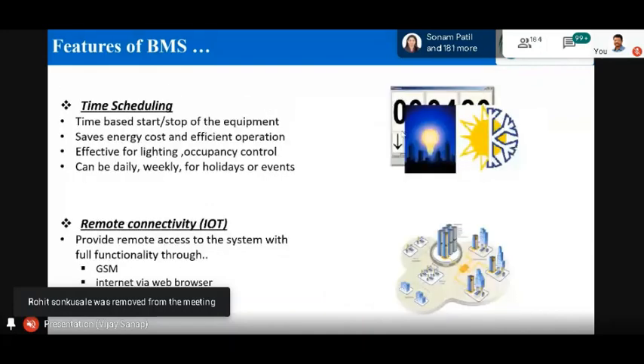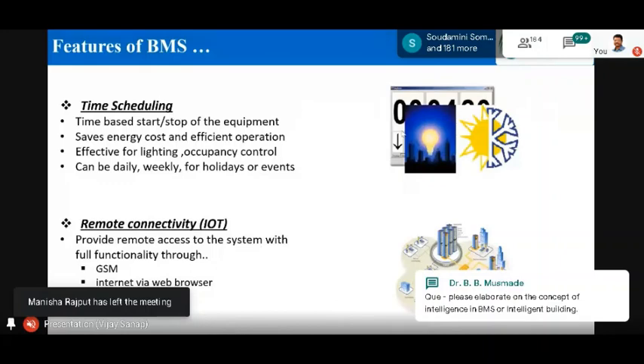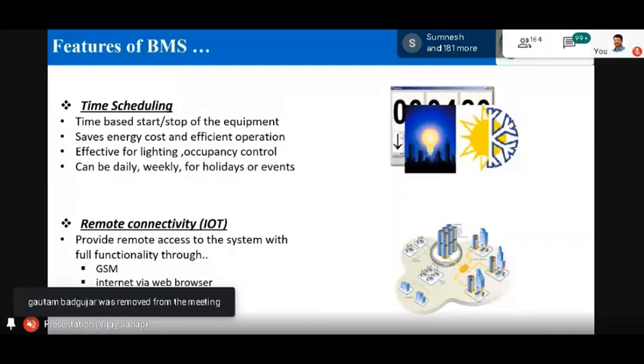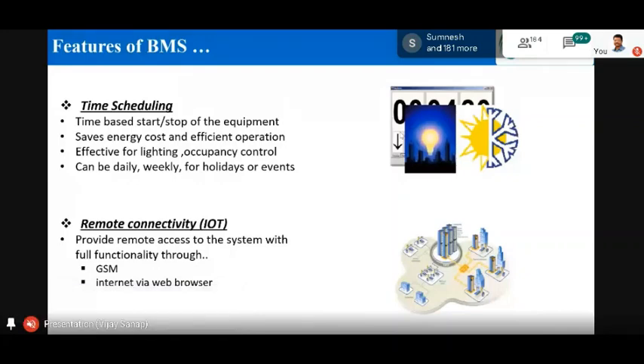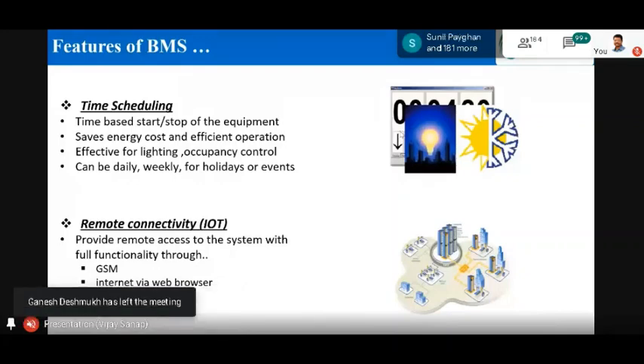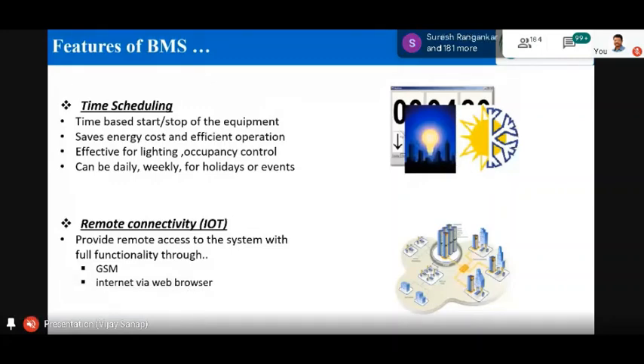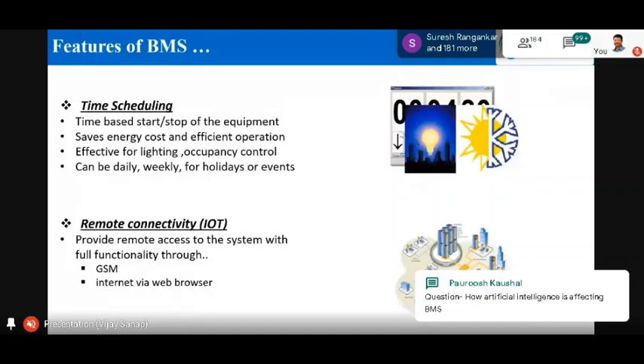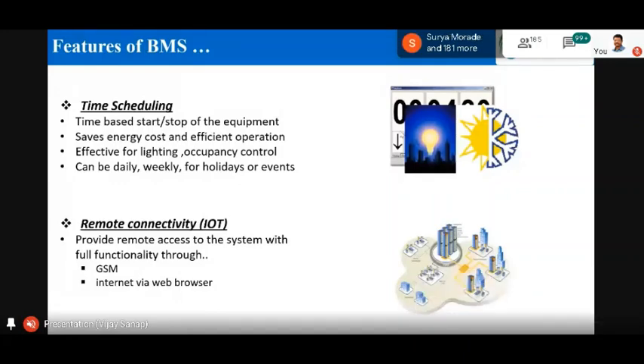Time scheduling is very important. If I have a big mall or an office like Infosys IT, many people are there, but they're off on Saturday and Sunday, so you don't want all the lights on, all the chillers on, or the entire AC on. Time scheduling takes care of that—it has calendar input and can account for holidays or seasons, so you can schedule equipment, resulting in convenience and a great deal of energy saving.